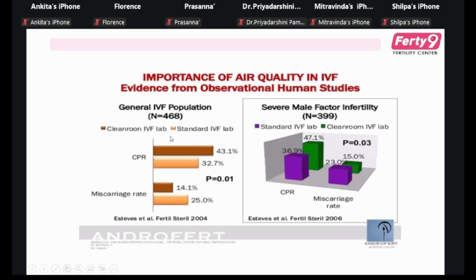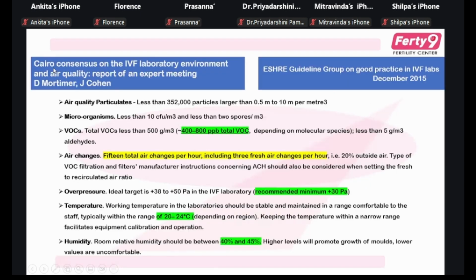Maintaining air quality is important for increasing clinical pregnancy rates and decreasing miscarriage rates, according to different standards. There are consensus guidelines like the Cairo consensus and ESHRE consensus that regulate how to maintain the ART lab. Air quality particles should be less than 352,000 particles, microorganisms less than 10 cfu per cubic meter, and VOCs should be 400 to 800 parts per billion total VOCs.